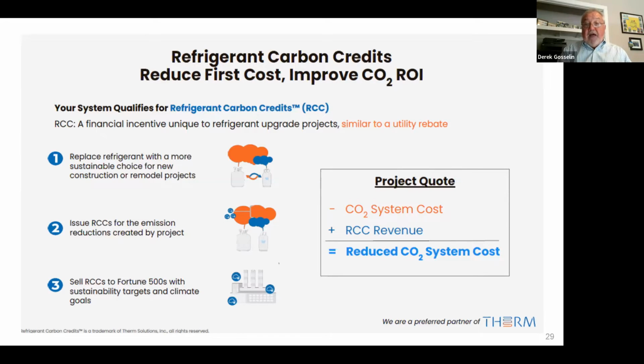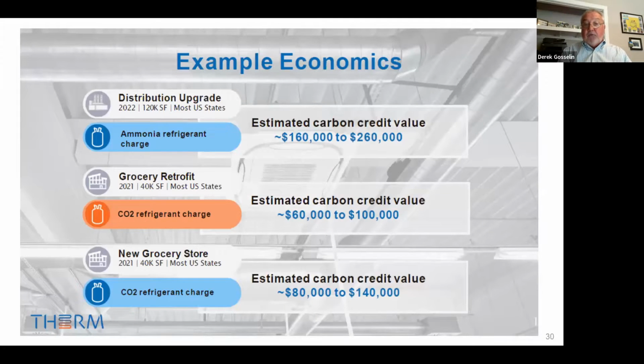How do we create value? That value can be there if you're doing a gas retrofit, getting out of a high GWP into a low one. It's not just limited to natural refrigerants, but there's a bigger bang for your buck by doing natural when you reduce the whole carbon footprint of the store. So how do we then take that into a value statement?